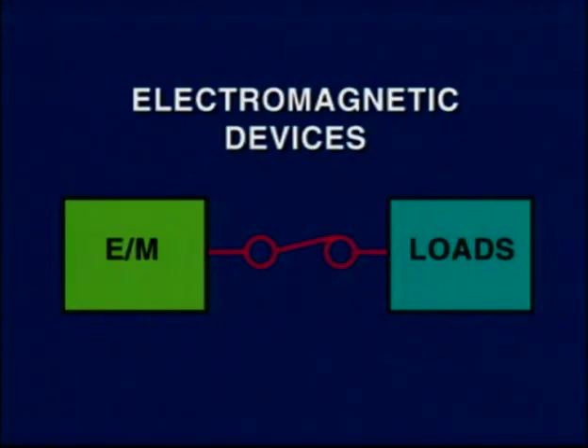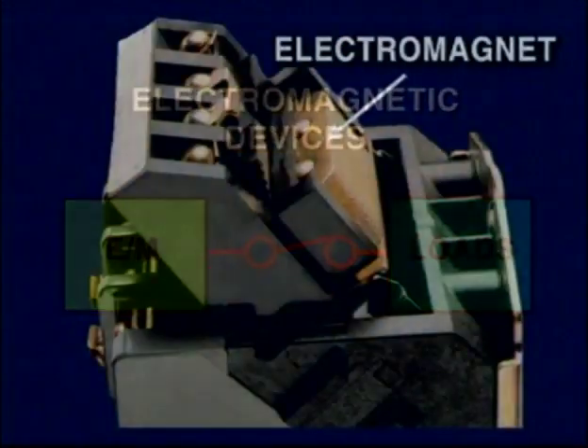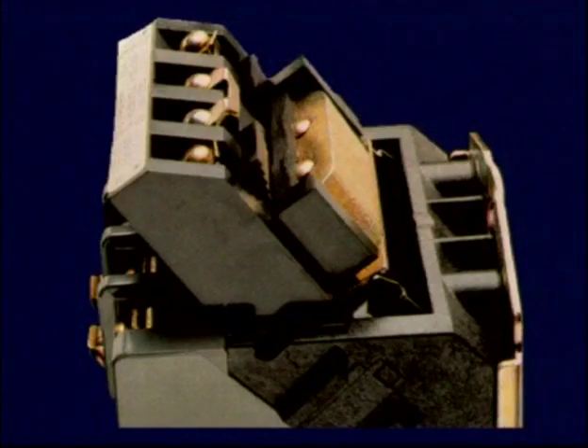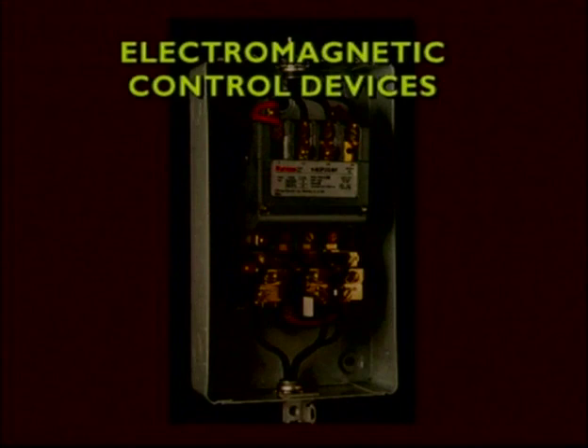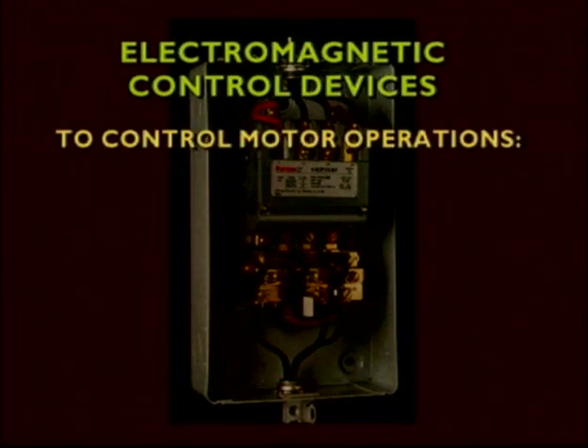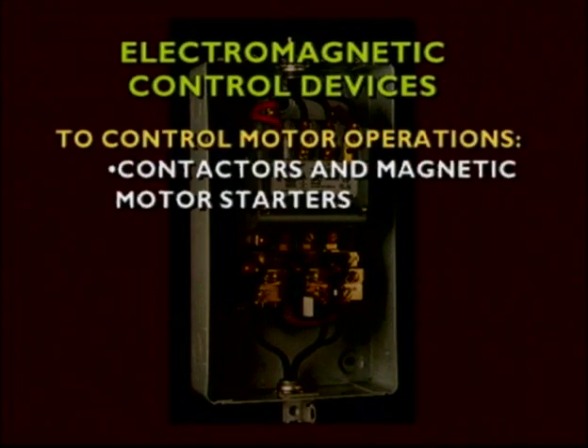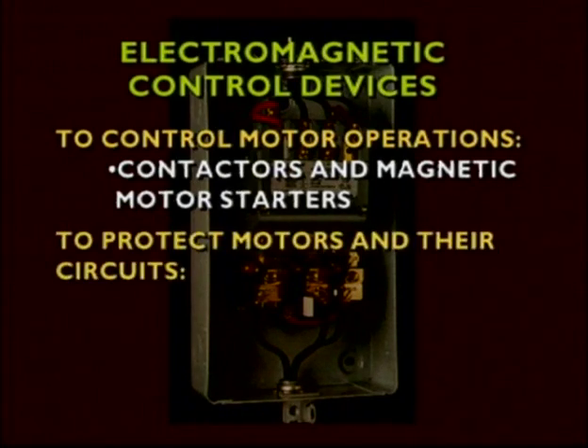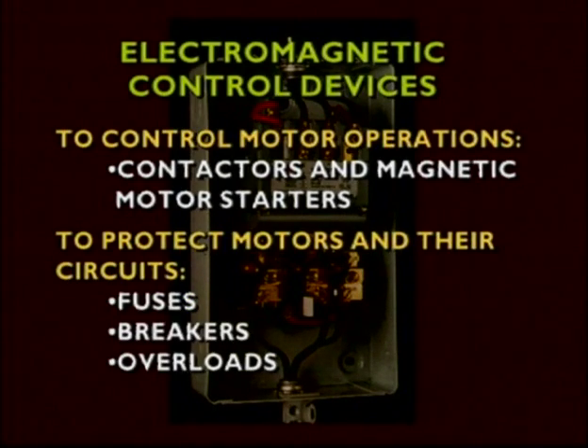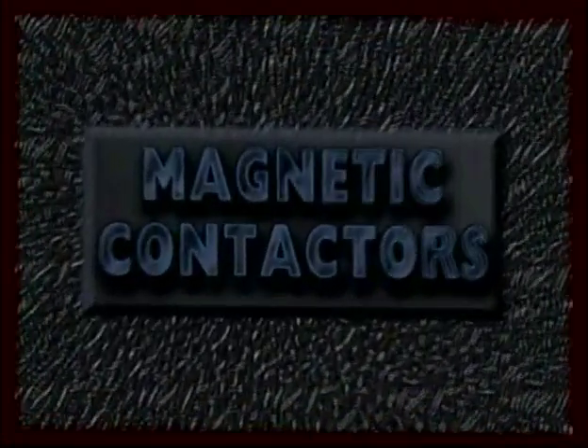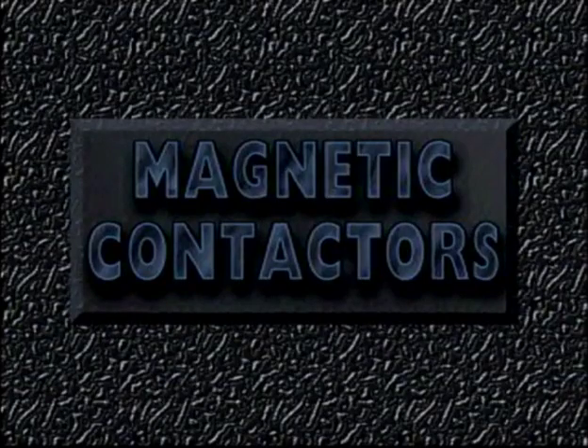These devices are called electromagnetic because they use a magnet and electrical power to actuate the switching mechanism. The electromagnetic control devices we'll cover, which are used in the control of motor operations, include contactors and magnetic motor starters. The devices we'll cover, which protect the motor and the motor circuit, include fuses, breakers, and overloads. Let's start by looking at contactors.